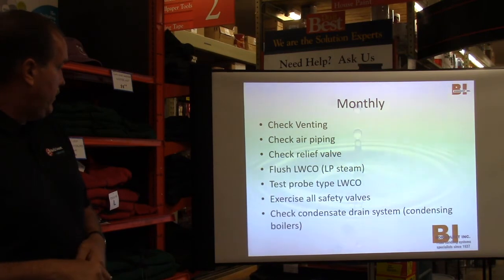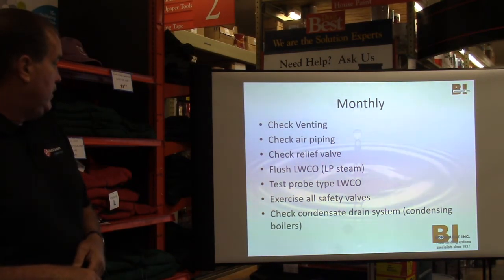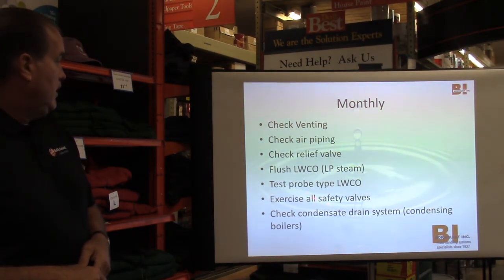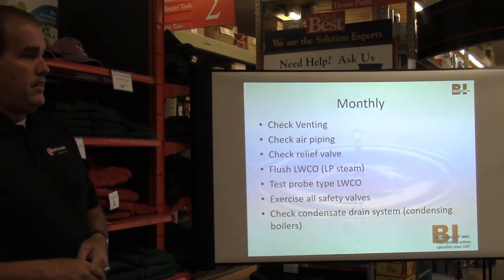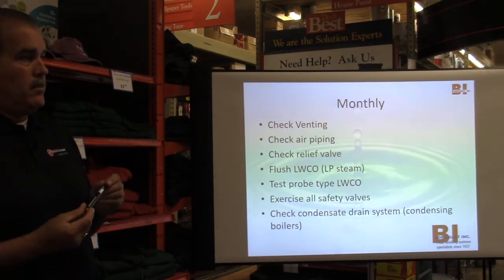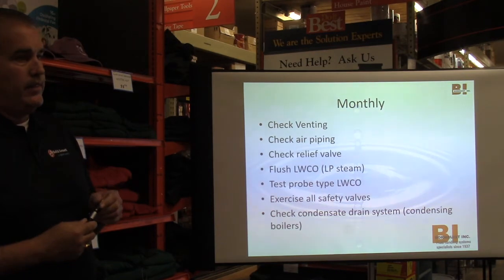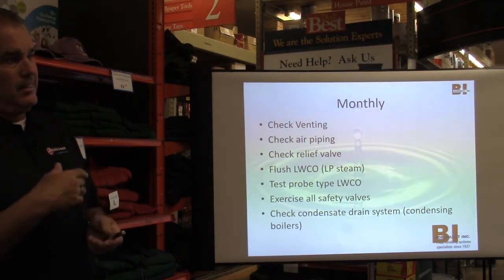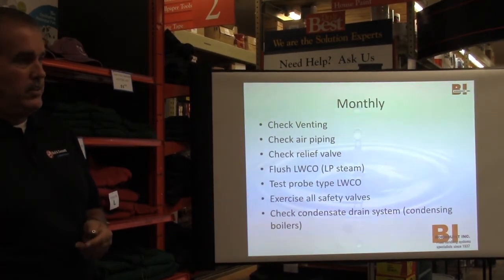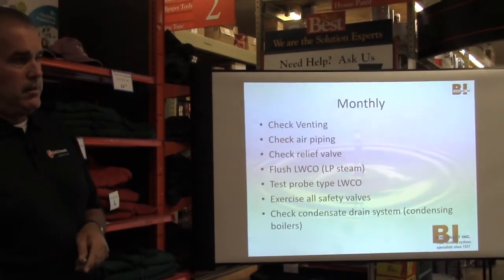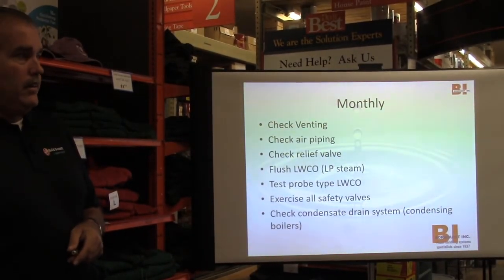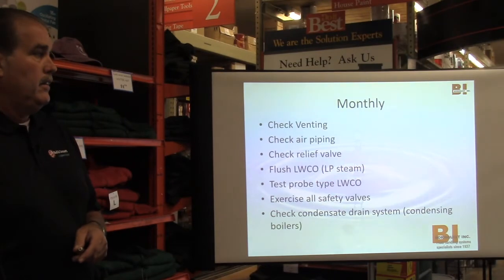We talked about the relief valve. We say exercise the safeties. Most residential safeties, you don't really have a lot you can do there to exercise. So this is kind of a commercial thing where there are more safeties to check. But on a residential application, there's really not much, except some low water cutoffs might have a test button.